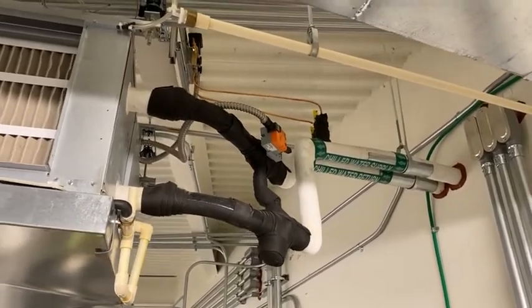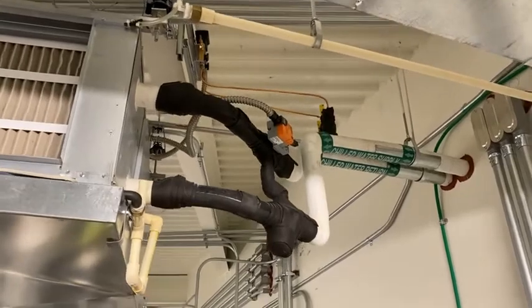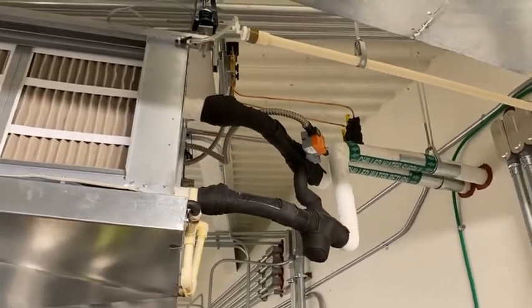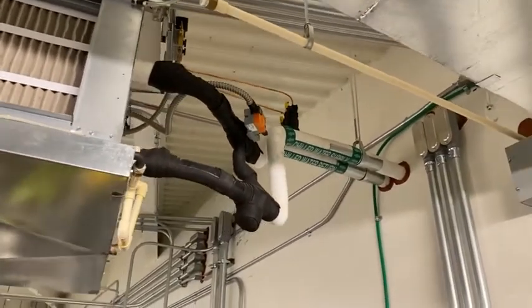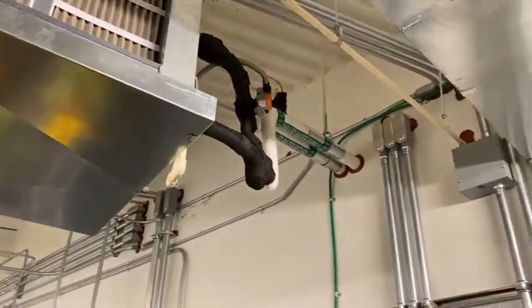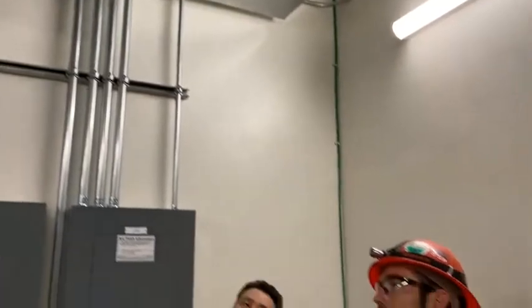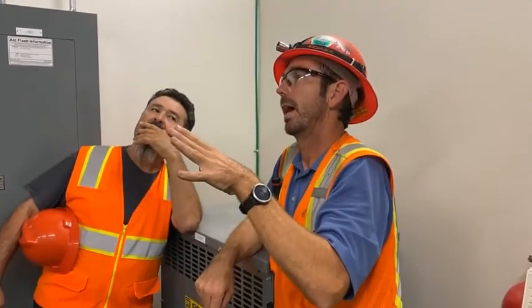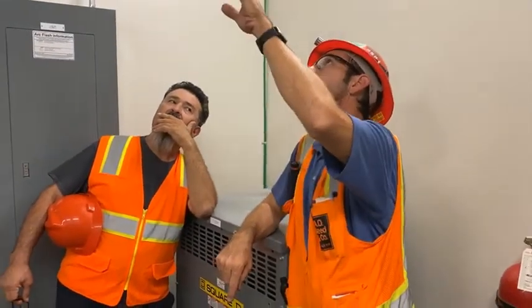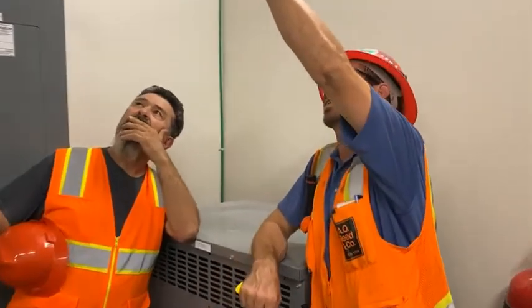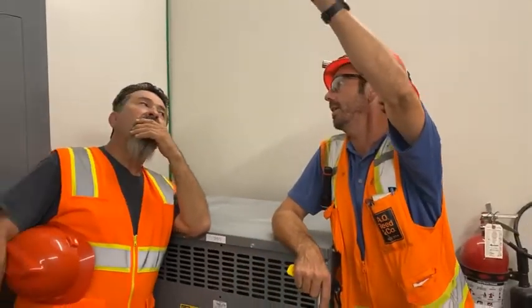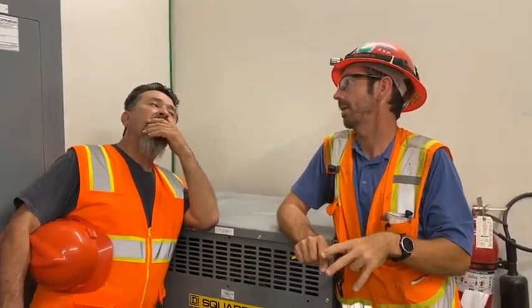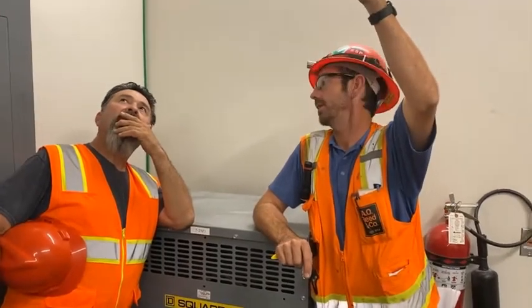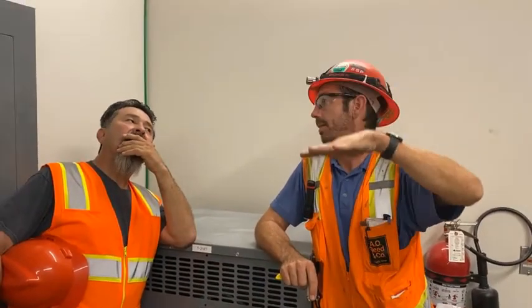What the balance guys did here is they verified all the units are flowing chilled water. We have 3 fan coils and 2 air handlers, okay? All of those units are open, the valve is open, and they get the total flow. Then they see what the differential pressure is here at that condition. They write that down and put that in the computer. Then as the valve starts closing, it will build up pressure and slow the pump down, okay?